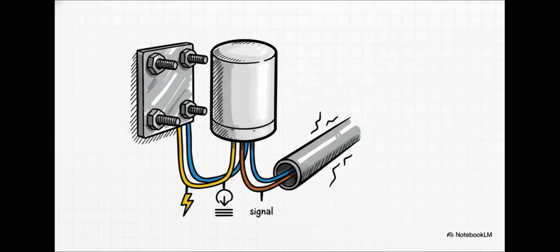Sensors can be either sinking or sourcing. A sourcing sensor provides power on its signal line when it's activated. A sinking sensor, on the other hand, provides a path to ground. The key takeaway is you have to match the sensor type to the PLC's input card. If you mix them up, the brain will never hear what the sensor is trying to say.